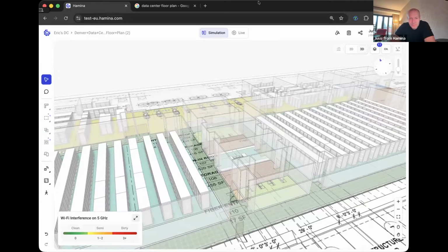You'd have all this infrastructure, usually telecom at the bottom and electrical on top, and if there's liquid cooling, that runs as well in there. So you've got to stack all these layers of services above the racks, and keep separation between them so you can walk on them. Between your rack and the ceiling, you need about 2 meters easily. Then above the ceiling you'd have services, and you need to use the ceiling as what we call an air return plenum, so the warm air from the servers can run back and be reconditioned as cold air essentially.